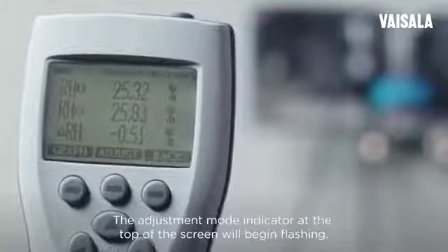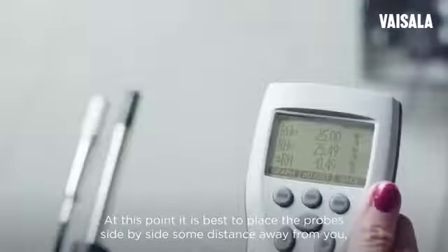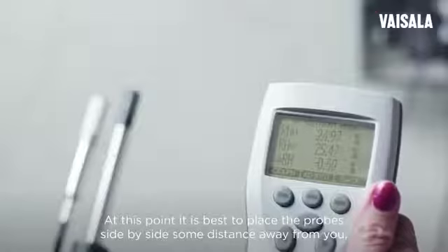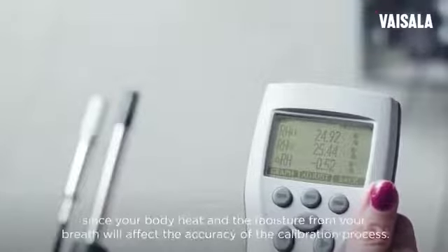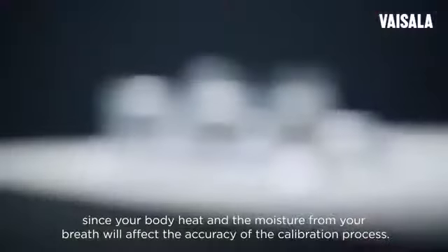The adjustment mode indicator at the top of the screen will begin flashing. At this point, it's best to place the probes side by side some distance away from you, since your body heat and the moisture from your breath will affect the accuracy of the calibration process.